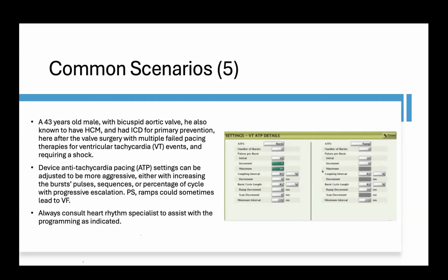What we can do in those cases is check the device antitachycardia pacing, or ATP, settings, and then we can adjust those, or at least give it a trial, to see if we can make them more aggressive by increasing the number of bursts, pulses or sequences, or by making the coupling interval shorter. So moving from 81 to 78 or 74, especially if the patient is connected to cardiac monitors and watched. Sometimes these aggressive ATPs are more successful in delivering the therapies and terminating the ventricular events.